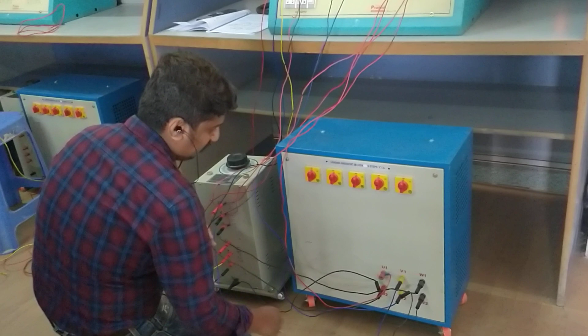Next, phase current. Again these three you have to short in star - these two, three - the secondary side should be shorted and come to neutral. Instead of direct shorting, I am shorting through an ammeter, so it acts as a phase. So U2 is going to the ammeter, phase ammeter, the other end is coming to V2, and V2 to W2 I have shorted, and this shorted point I have given to neutral.